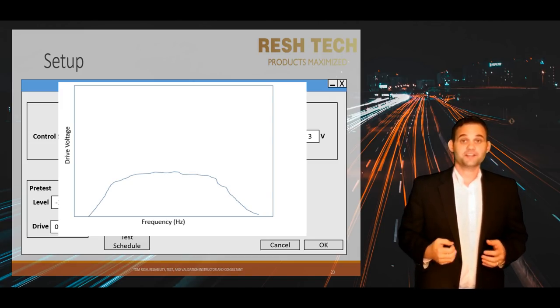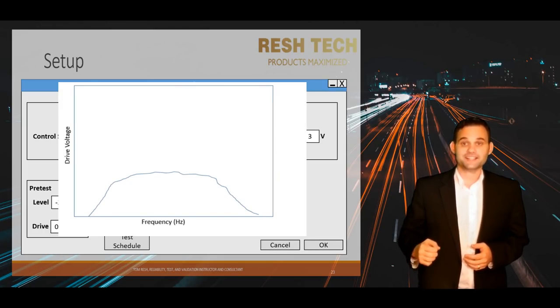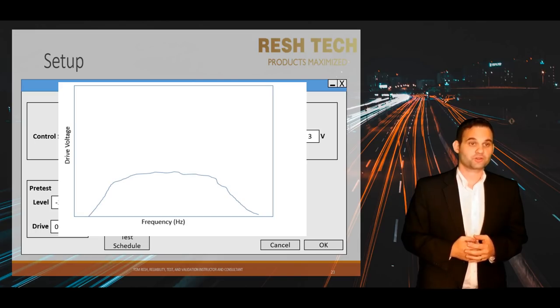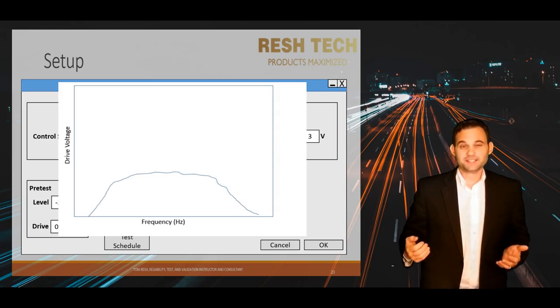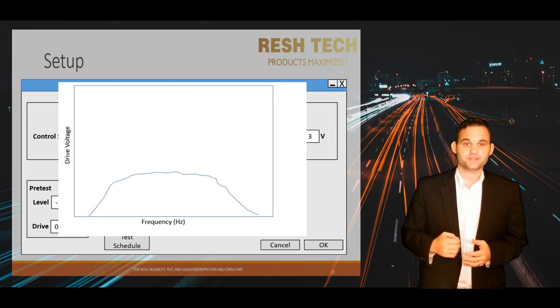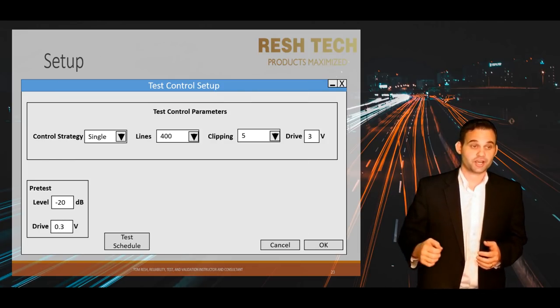Next up is the drive voltage limit. This is another way to protect your product and your shaker. Set the voltage only as high as it needs to be to run the test. Even if your vibration test system is capable of running a max drive signal of, for instance, 10 volts from your vibration controller, it doesn't mean you should set every single test to 10 volts. Don't do that, or you can break your test unit and possibly damage your shaker.